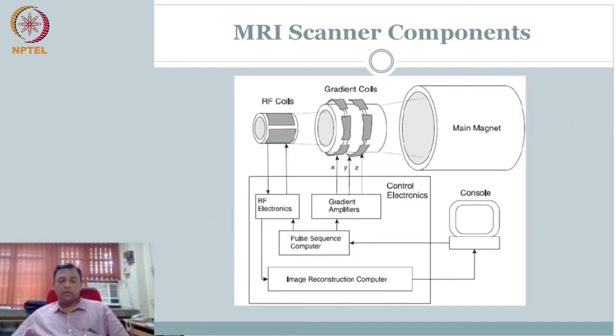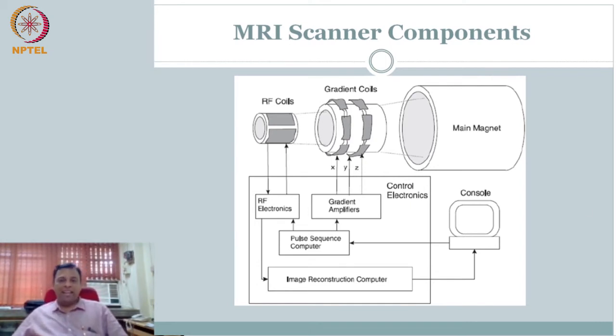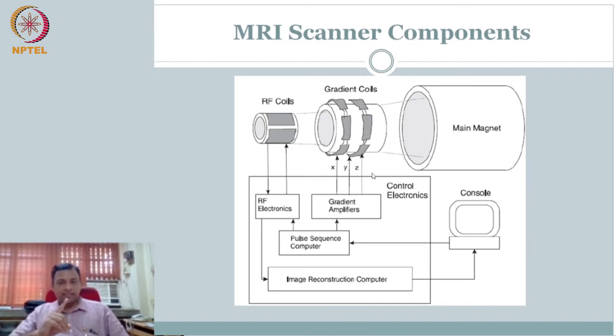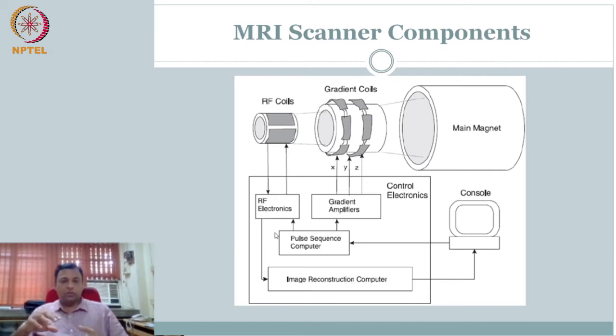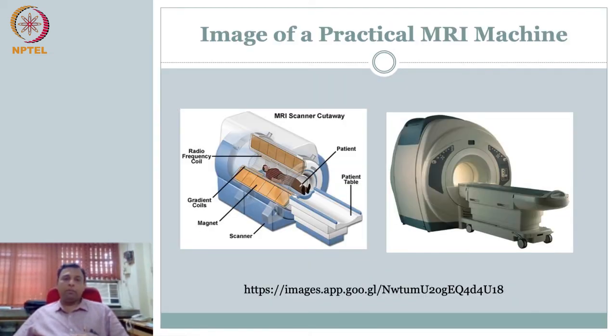How do we enable this? This is a block diagram of the components. You have a main magnet, gradient coils — gradient means slope, a change in something, and here that something is the magnetic field. You have gradient coils in XYZ to change the magnetic field at different locations. Then you need RF coils to apply excitation and receive signal. You also need a sequence computer to code the pulse sequence programming we talked about. Then you do image reconstruction, and you have a big console controlling all of this. This is a typical MRI — you have a bench, a big door, and the patient goes in.